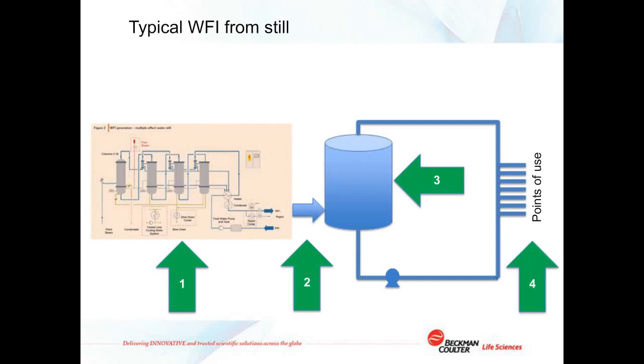Points of use that require cool or cold water, either for process reasons or for the safety of the personnel, have to have the water cooled using heat exchangers, which again consume energy. And as the points of use are effectively small loops in themselves, any water that's not used circulates back into the distribution loop, and this has to be reheated back up to above 65 degrees centigrade before it enters the loop. Periodically, the water in the storage tank and distribution loop has to be heated up to temperatures higher than 80 degrees centigrade to hold back the formation of biofilm inside the pipework.